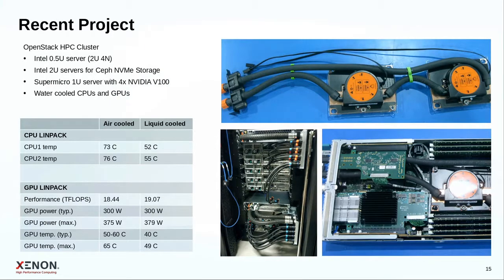This is an example of a recent project we delivered to one of our research customers. We've been using high-density half-U servers, 2U 4-node solutions, shown in the photo here. We have the pump assemblies with the cold plates, and tubing that goes out using one of the PCIe slots in the back. In this case, we were able to integrate that with Socket Direct ConnectX 6 Mellanox and ConnectX 5 Mellanox adapters, routing the tubing through in between. When we tested this, running a CPU LINPACK, we were able to reduce the temperature of the CPU packages by about 20 degrees with this setup and technology.